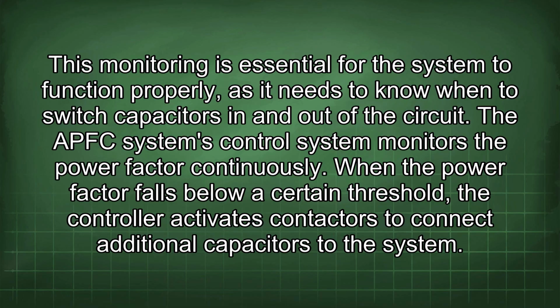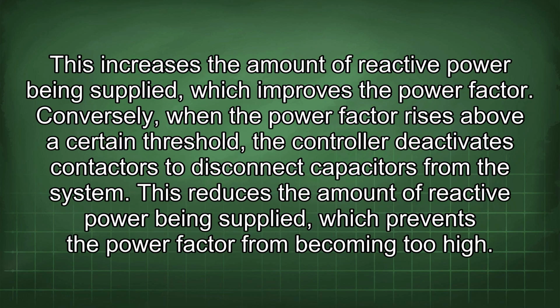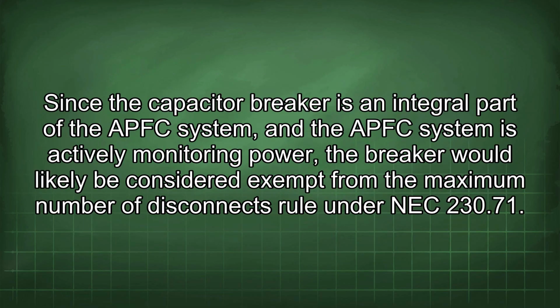When the power factor falls below a certain threshold, the controller activates contactors to connect additional capacitors to the system. This increases the amount of reactive power being supplied, which improves the power factor. Conversely, when the power factor rises above a certain threshold, the controller deactivates contactors to disconnect capacitors from the system. This reduces the amount of reactive power being supplied, which prevents the power factor from becoming too high. Since the capacitor breaker is an integral part of the APFC system, and the APFC system is actively monitoring power, the breaker would likely be considered exempt from the maximum number of disconnects rule under NEC 230.71.